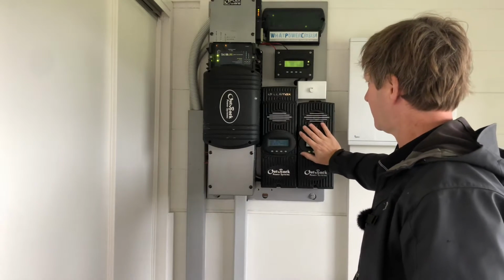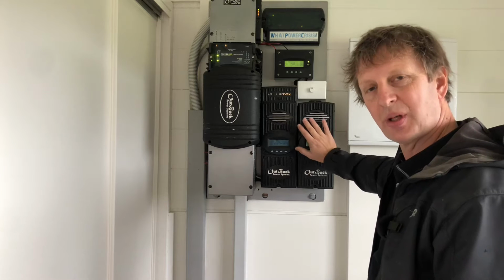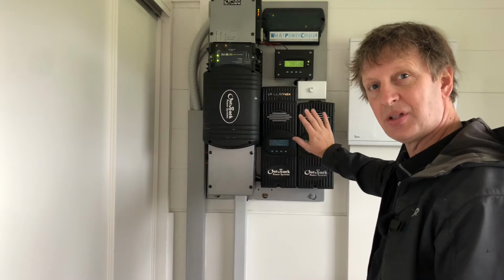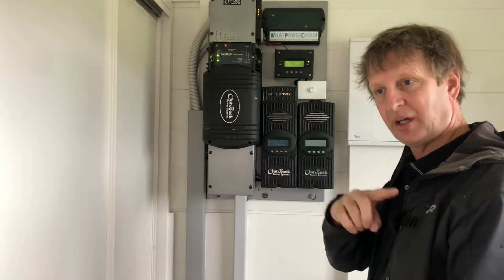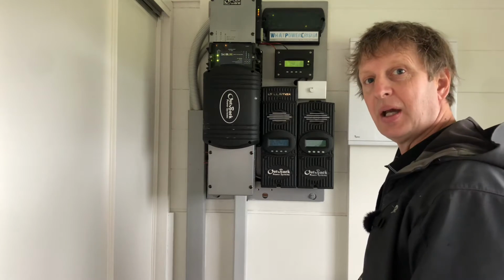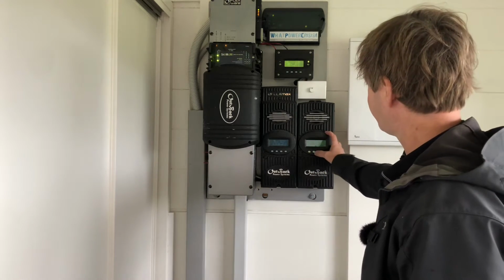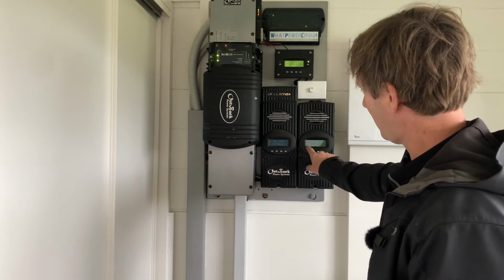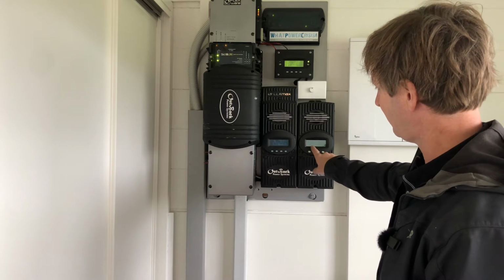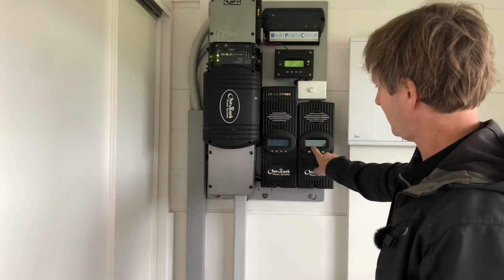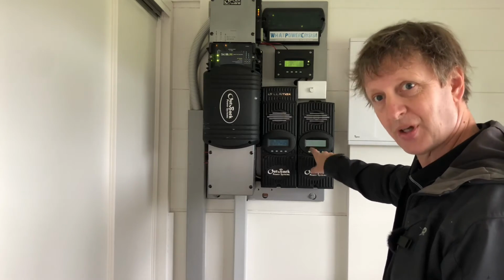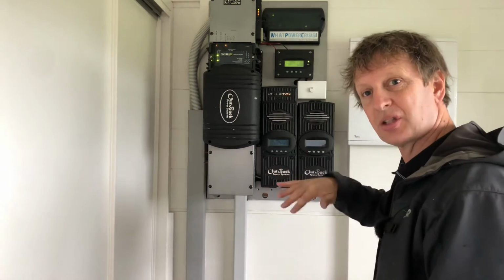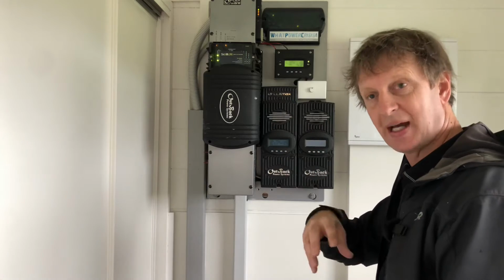There is an output on this charge controller, so when the battery voltage gets low, the generator will automatically start, provided it's in automatic mode at the generator itself. That is controlled by the auxiliary output. If the aux is on, then the generator is off, so it's the other way around, and if the auxiliary turns off, the generator will start.